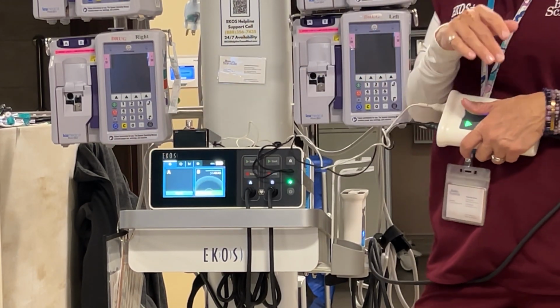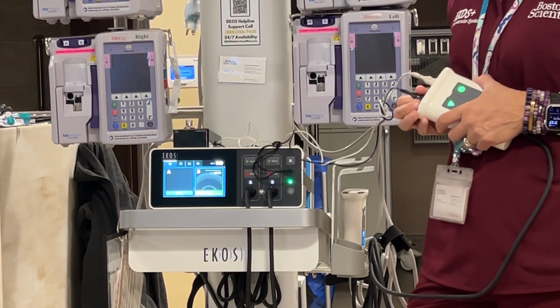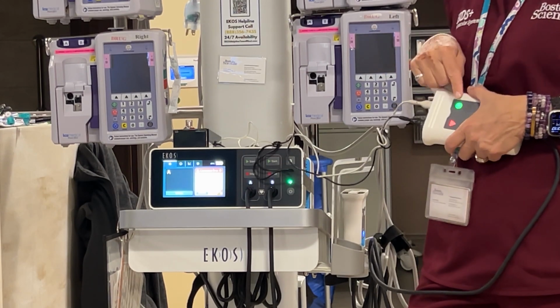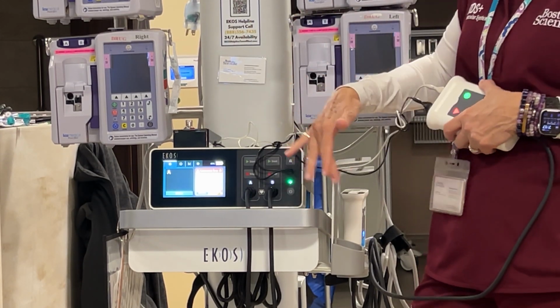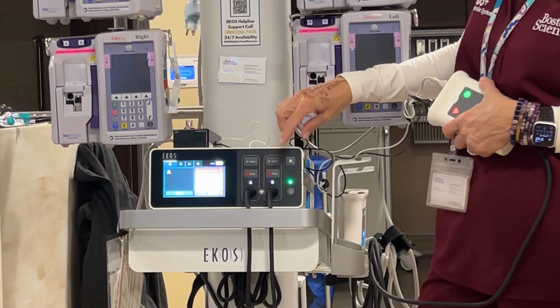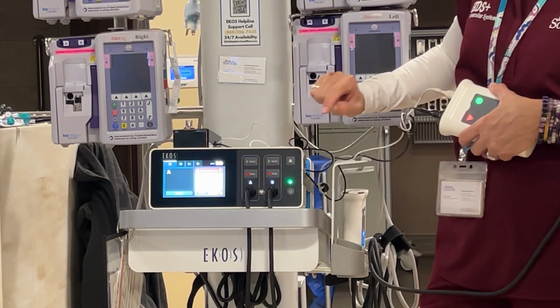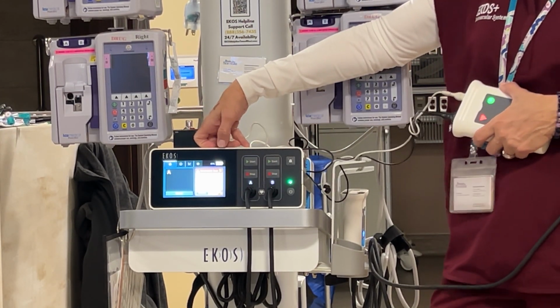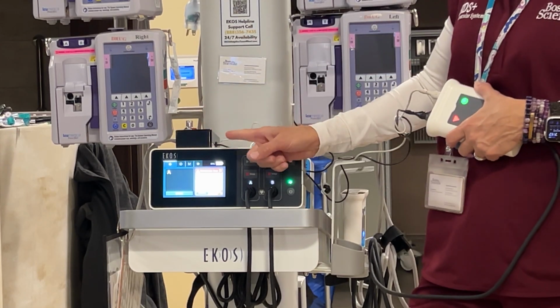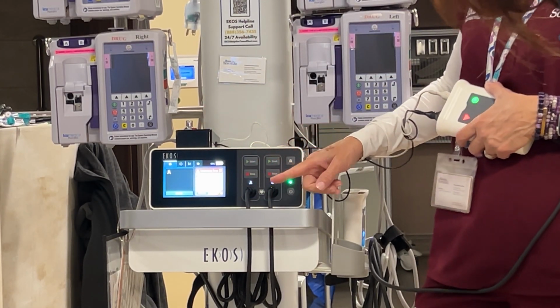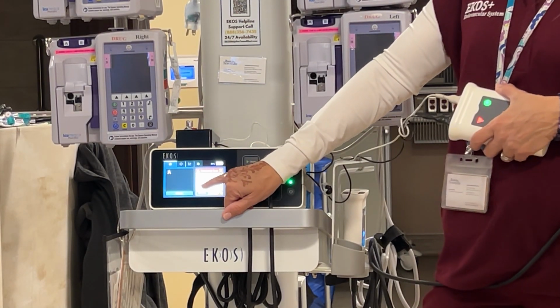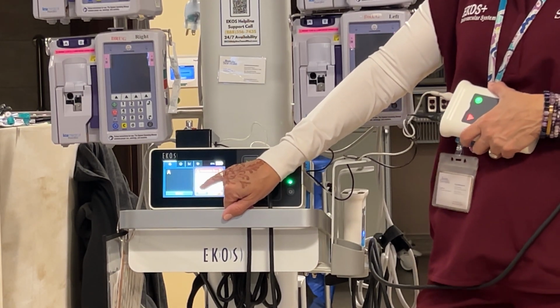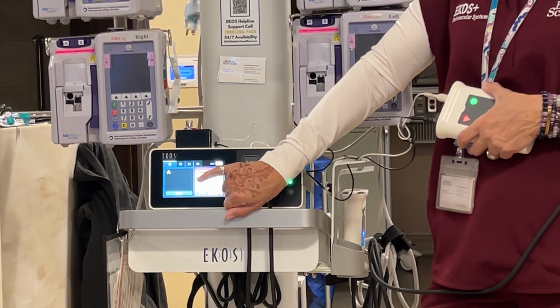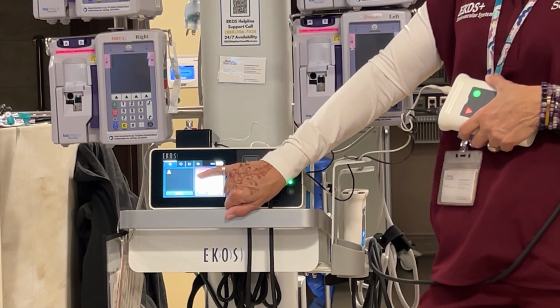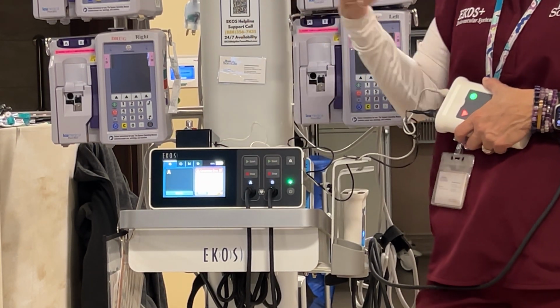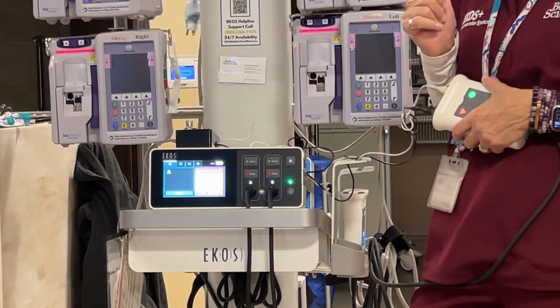So you always want to be on the home tab, and let's just say for whatever reason, it turns red, obnoxious noise. So I'm going to hit the mute button here. It says we have a connection error. It documents the runtime, and it gives us our troubleshooting right on the screen. Now at the bottom of the troubleshooting, it gives an E code, the letter E and a number. That E code you'd want to have available if you ever call the helpline, because it helps us follow the proper algorithm to get you guys up and running as quickly as possible.